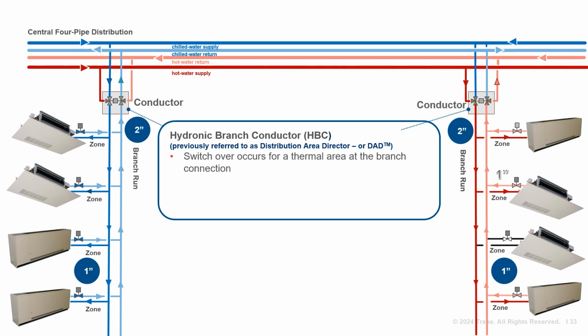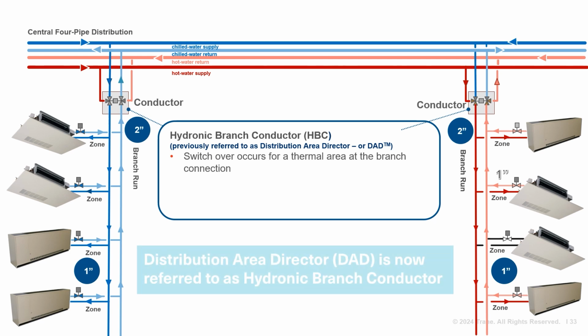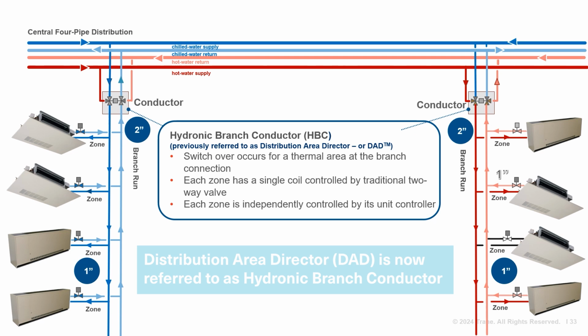This switch to heating from cooling or from cooling to heating is accomplished by a distribution area director, or DAD. This valve control unit directs either heating or cooling fluid to and from the area based on the current need, and there's no additional piping or valves required in the zone. Each zone-level terminal unit is controlled with a traditional two-way modulating valve, but now it has only one valve per zone. It is important to note the DAD does not control the zones.